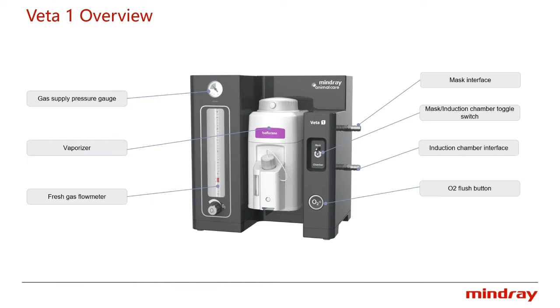This is the overview of Veta 1. Very simple, right? It contains a gas supply pressure gauge, one vaporizer V60, and also here is the oxygen fresh gas flow meter. This is the O2 flush button, and we also have two interfaces here. One is for the mask, one is for the induction chamber. Also, we got a switch here to choose these two channels. So that's all about the overview of Veta 1.